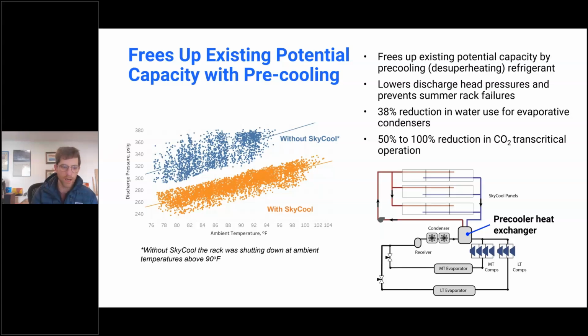And so you can see data, this is discharge pressure from a store in the Midwest, but essentially this condenser was underperforming. They've added cases, so there's a lot more heat that it needs to reject. They've added sprinklers to the system, so it's also got a little bit of corrosion on it. But anyway, by adding the panels, we're essentially able to lower the discharge pressure, and that allowed the system to operate actually at higher ambient temperatures. Previously, it would shut down, and they'd have issues with compressors locking out when the discharge pressure went above 380 psi. But in the context of HFC cooling systems, so 410A, 404A, it will save energy, it adds capacity.